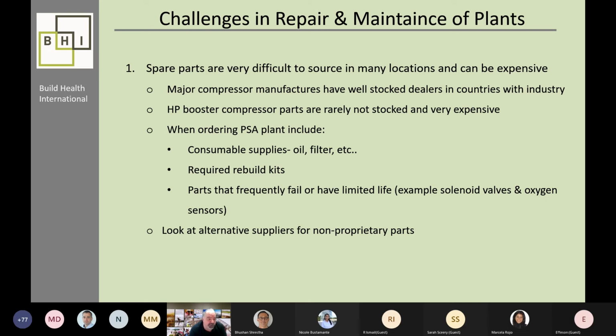The high pressure booster compressors, which are made by only about 3 companies in the world, perhaps a few more recently, are rarely stocked and very expensive. These booster compressors take the oxygen and compress it from 50 or 100 psi to 2200 psi or more for filling cylinders.